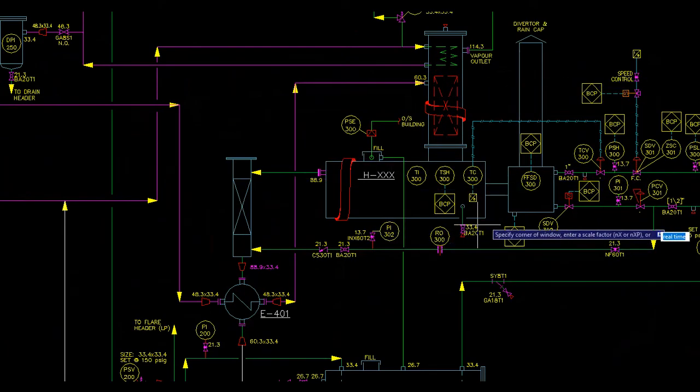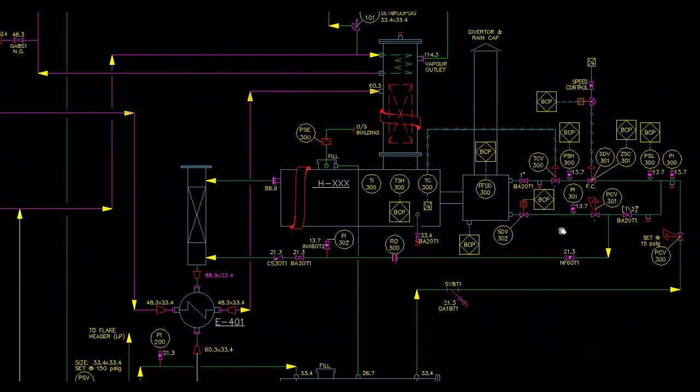In the reboiler, the temperature is maintained at 400 degrees Fahrenheit or 205 degrees Celsius. Water boils at 100 degrees Celsius, so there is enough temperature for water to exit as steam through the reboiler column. This is how rich glycol becomes lean glycol.